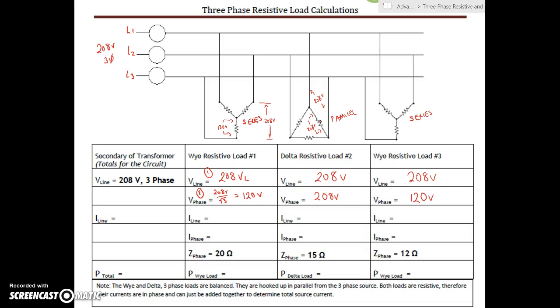Now, the next step we need to do is find our phase current. So we're going to break each of these three phase circuits down into just a simple Ohm's Law equation. Here we have 120 volts divided by 20 ohms. That's going to give you 6 amps. Here we've got 208 volts on the phase divided by 15 ohms.